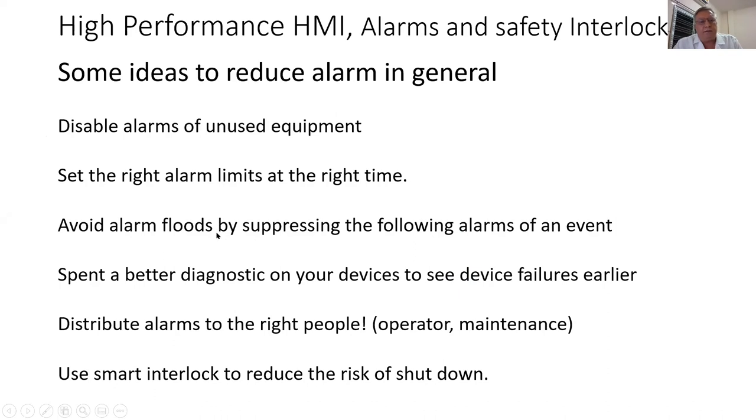The other is alarm flood. Let's say you have a pressure, a flow, or some other alarms, and your pump has a problem. Then you trip maybe on a pressure, but then your flow alarm also will appear. But this is only a following alarm. It is not important to see that alarm, because if you know the pump is stopped, the flow doesn't matter. So you don't need an alarm for that. You see your pressure was too high. That's why it tripped.